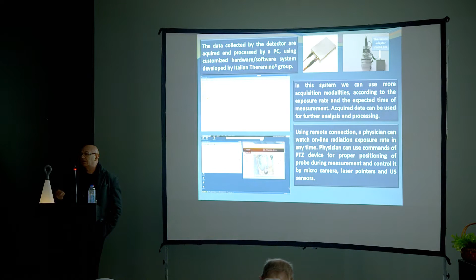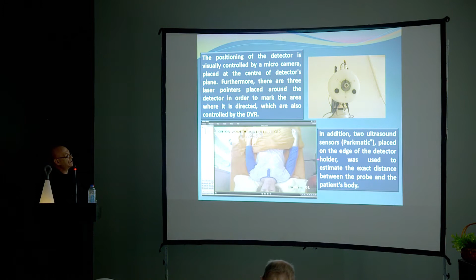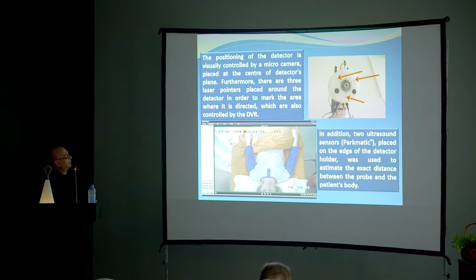Using remote connection, the physician can watch the online radiation exposure rate at any time from any place and can use commands of the pan-tilt zoom device and digital video recorder to check whether the measuring position is proper or not, and correct it. We can see on those pictures the actual count rate from the patient's body and live video from the micro camera.